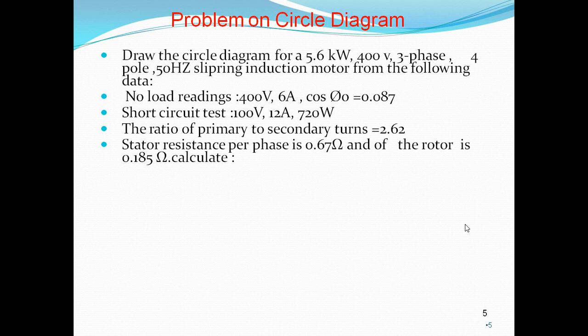By using belt and slip rings, we tighten the rotor so that it does not rotate. We raise the voltage slowly until the ammeter reads full load current, which we obtain at a very low voltage, about one-fourth of the rated voltage, and take the readings of ammeter, voltmeter and wattmeter.